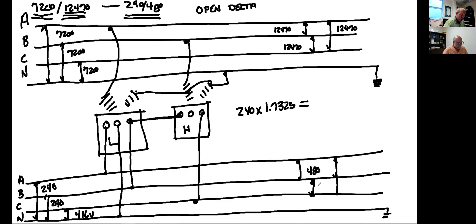Am I finished? No. What am I missing? You gotta multiply. Oh wait, yeah, no, you're finished. Yeah, we got that. Okay, that's the only time we need to multiply by 1.7325 is in a delta high leg. Delta high leg, the phase to ground voltage gets multiplied by 1.7325, and that is 416. We satisfied that down there. I'm finished. Okay, that's all there is I need to do there.